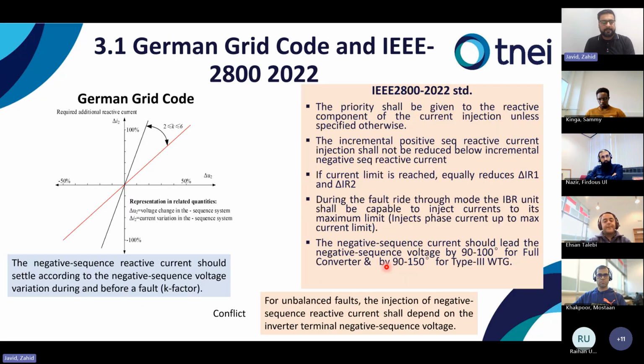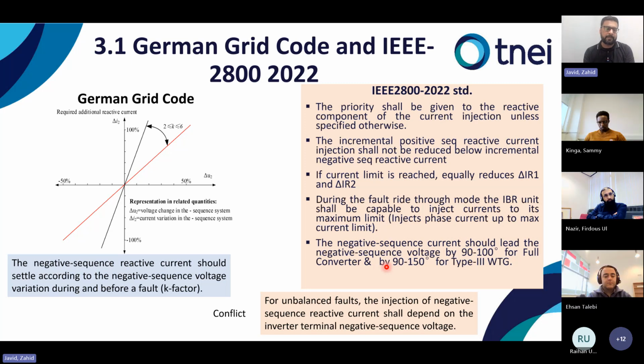So on the left hand side, there is the German grid code. It says that when there is an unbalanced fault in the network, the negative sequence reactive current should settle according to the negative sequence voltage variation during and before the fault, according to the K factor. So what does it mean? It means that if there is a fault and there is a difference in the negative sequence terminal voltage, the negative sequence current should be that voltage multiplied by the K factor.